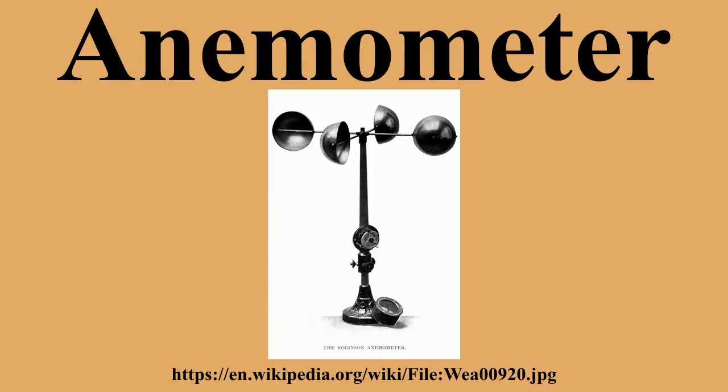When Robinson first designed his anemometer, he asserted that the cups moved 1/3 of the speed of the wind, unaffected by the cup size or arm length. This was apparently confirmed by some early independent experiments, but it was incorrect. Instead, the ratio of the speed of the wind and that of the cups, the anemometer factor, depends on the dimensions of the cups and arms, and may have a value between 2 and a little over 3. Every previous experiment involving an anemometer had to be repeated.